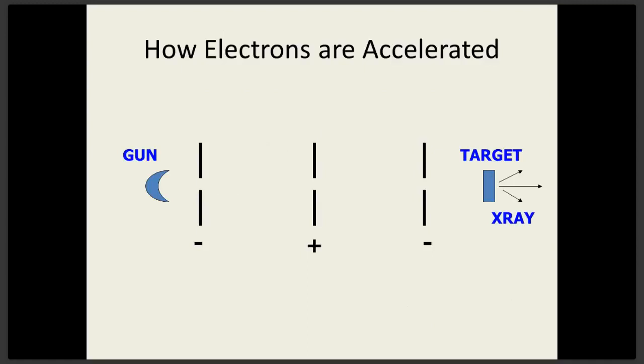The electrons hit it on the backside. Bremsstrahlung radiation comes out the front side. So not like a beveled target in an X-ray tube. Very, very different. Transmission target. Electrons are accelerated at near the speed of light, passing through a series of cavities, slam into a piece of tungsten. Now, how do you get electrons to accelerate?